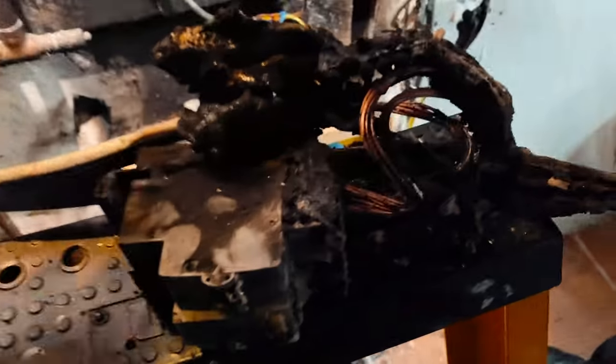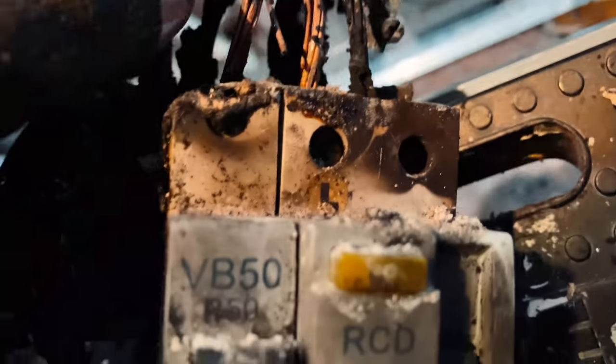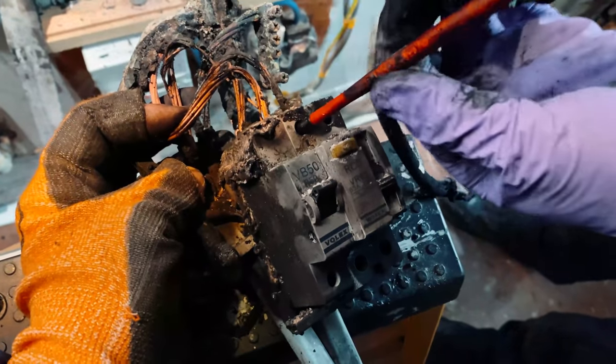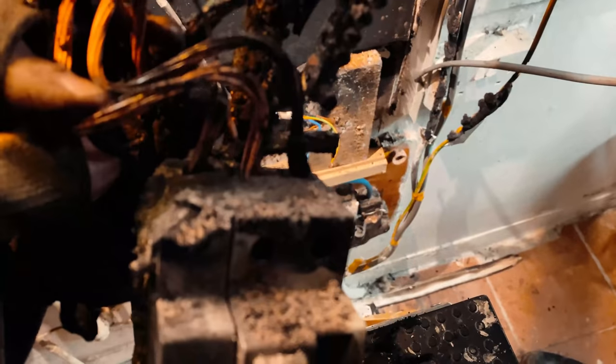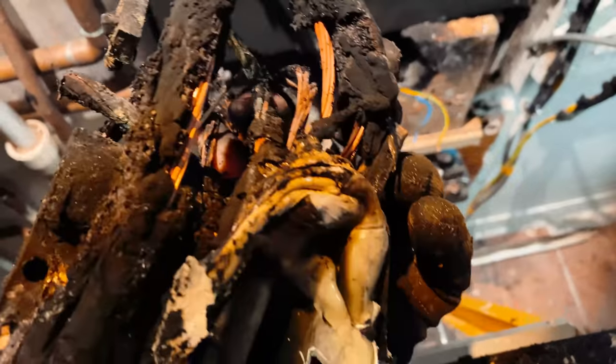What we've discovered is that the live wire incoming into the RCD is actually loose — see that? It's loose. The neutral is tight in the terminal, but the live is loose. If we put a screwdriver on it, it's actually loose enough that you can just tighten the screw. That looks like the problem — it was a loose connection on the incoming live conductor. The outgoing live is tight. Corey, can you check the terminals on the busbar? Bus bar terminals are tight — yeah, they're good, so it's not that. But serious meltage has happened there.